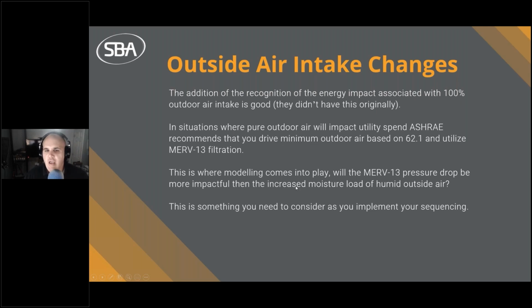In some cases, you will have capacity in your central utility plant to handle the increased enthalpy load of outside air. In other cases, you may have the capacity in your fan systems to handle the pressure drop of MERV 13 filters. Only you know your building and your systems and what they're capable of. So you'll have to model out: can we afford a 1-inch water column pressure drop? Or can we handle a reduction of delta T from 12 degrees to maybe 8 degrees across the coil because of the humid outside air? You need to think about this prior to implementing this.